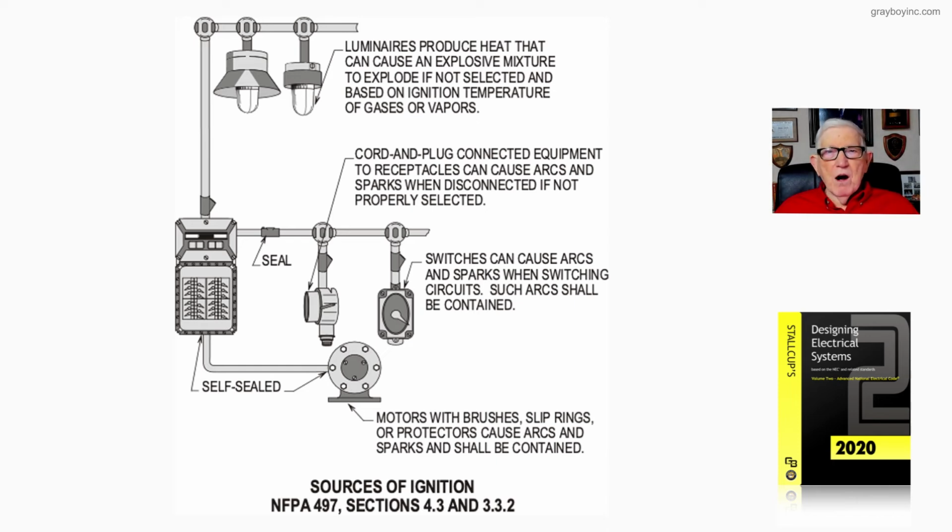Now, we know from our experience as designers and electricians that we try to design with an enclosure that is rated for Class 1 Division 1, if that be the case. And there's explosion-proof enclosures, purged and pressurized type enclosures, and intrinsically safe in accordance with Article 504. And that's Class 1 Division 1 areas, when our equipment can be put in those areas.